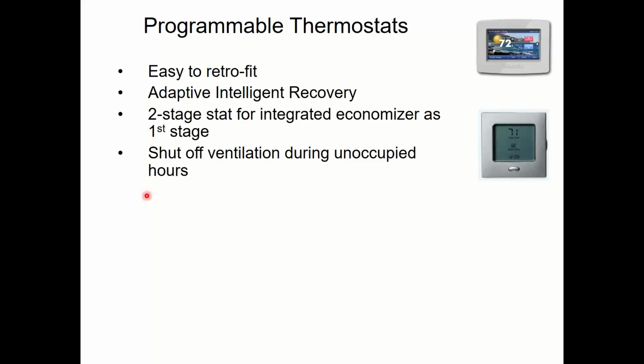You want to get a stat that'll also shut off the ventilation system during unoccupied hours. This is required by code on modern systems, but people don't really understand it. The vast majority of thermostats out on the market do not do this. The thermostat at your building is not doing this now. Every time your thermostat asks for heating or cooling in the middle of the night, even though you have relaxed set points, it still opens up the ventilation damper because your ventilation damper doesn't know if it's daytime or middle of the night. It just knows the fan turned on, and if the fan turned on, it opens the damper.